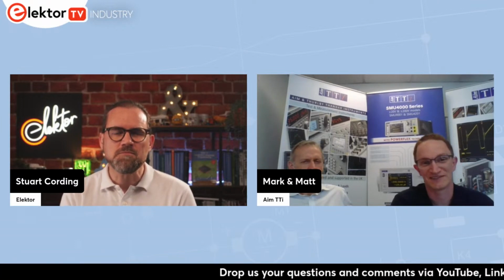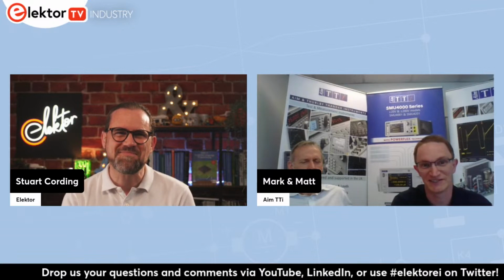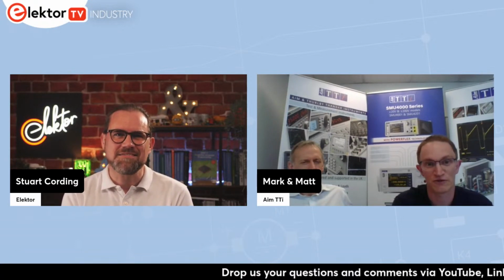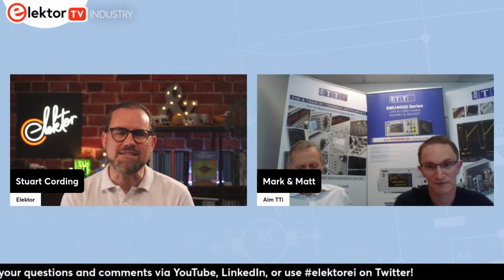That delay can have significant effects on your measurements. Basically, if you measure too soon, you're going to see your rise time, which you don't really want to do. If you measure too late, you're wasting time. So it's about optimizing that auto delay to give you exactly when that source level has stabilized after 300 microseconds.